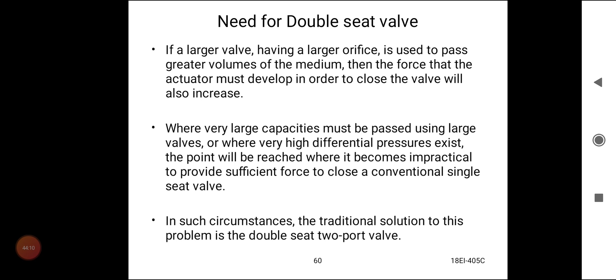Here we can see double seat plug valves. There are two seats and two plugs in the valve body. The fluid passes through the port openings of these two seats. The two plugs are attached to the stem. When the stem moves, the plugs also move, so the opening area of the seats can be varied using these two plugs.